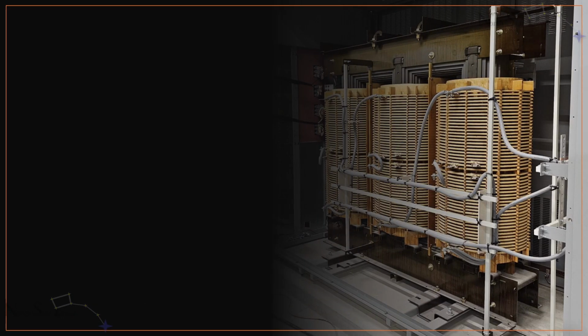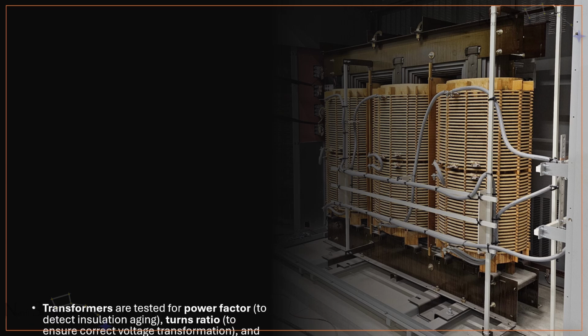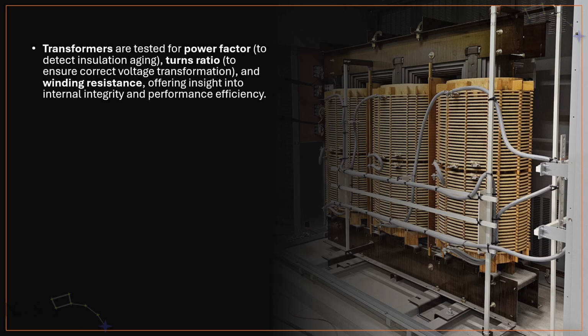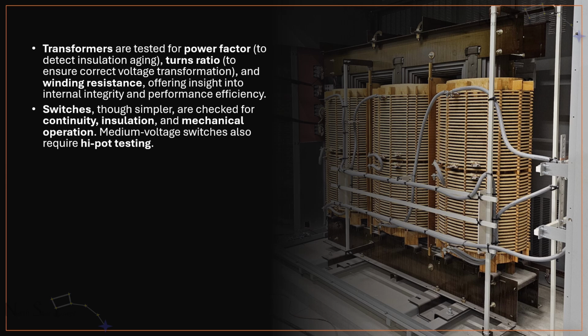We mainly focus on circuit breakers, but other components have similar tests that verify their function in different ways. Transformers are tested for power factor to detect insulation aging, turns ratio to ensure correct voltage transformation, and winding resistance, offering insight into internal integrity and performance efficiency. Switches, though simpler, are checked for continuity, insulation, and mechanical operation. Medium voltage switches also require high-pot testing.